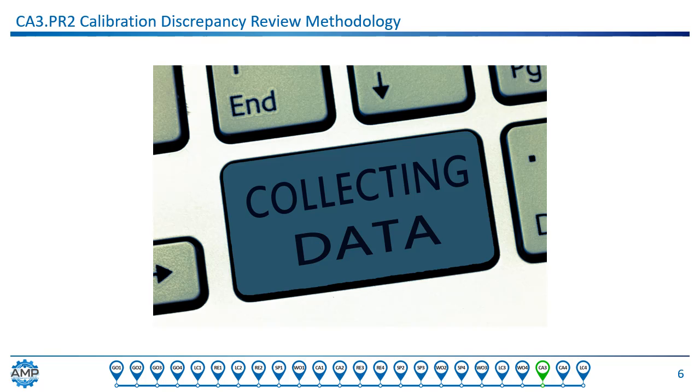Data collection. Sources of out-of-tolerance investigation data should be identified within the process. There should exist a list of sources that permit collecting calibration data to identify what functions, parameters, ranges, and test points were found out of tolerance. Other information necessary to conduct the investigation is when the instrument was last known to be operating correctly, where the instrument was used during the potential duration of the out of tolerance, and how the instrument is used. When all information is collected, the impact of out of tolerance can be estimated.